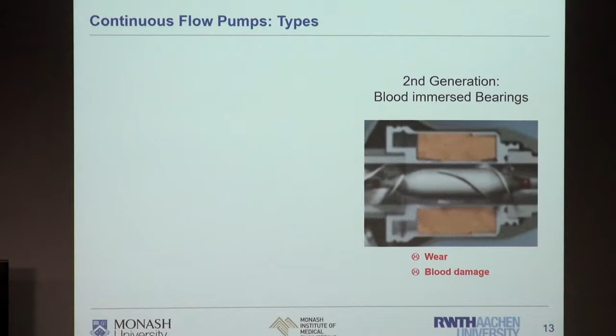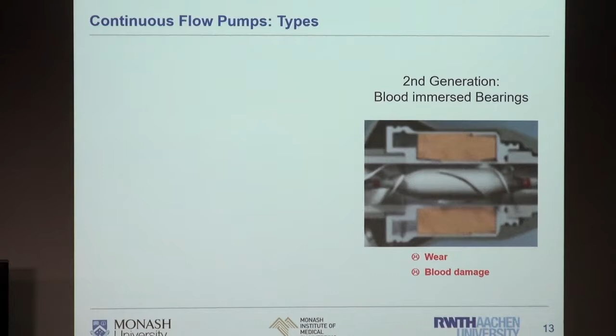We had to keep the rotor somehow to rotate. But that has a disadvantage because wherever you have a bearing, you have wear, and these pumps have to run a long time. Think about life expectancy, and we have blood damage because the red blood cells get in there and they get squeezed and they get damaged. So what we do nowadays is we have fully suspended rotors, for example with magnetic forces, we keep the rotor in balance all the time.